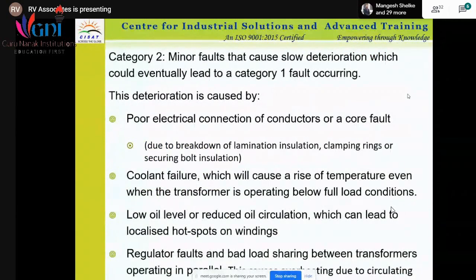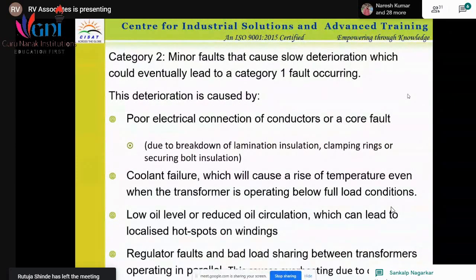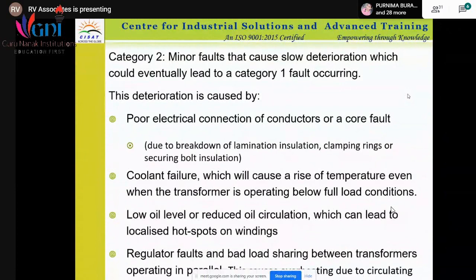Then there may be some minor faults. Minor faults, what is it? It's a slow deterioration, like temperature rising. Because of the temperature, there will be sludge formation. Sludge formation may lead to blockage in the fins of the cooling system or tubes, pipes. So slowly it increases, and then at one stage it may lead to the fault. There may be a coolant failure. Coolant is not moving properly, so there will be a rise in temperature in the transformer, or in any of the various parts like pumps, fans. Then there are many instrument systems. WTI, temperature indicators, instruments are there, terminals are there, sensors are there. So anything can fail. So those are the minor faults.